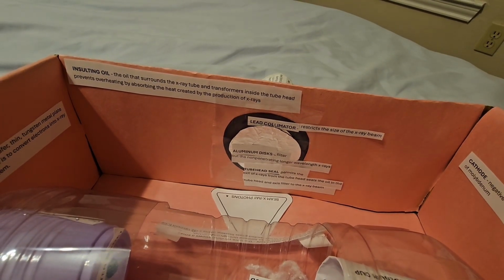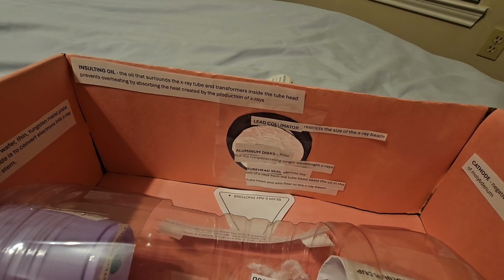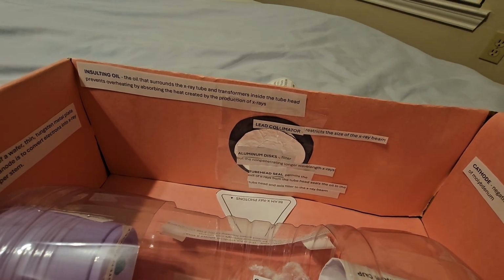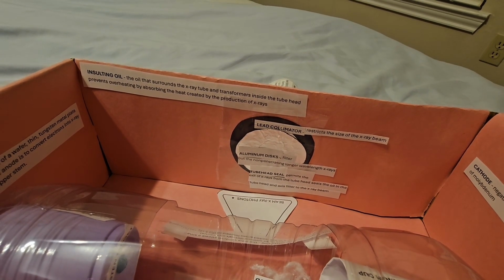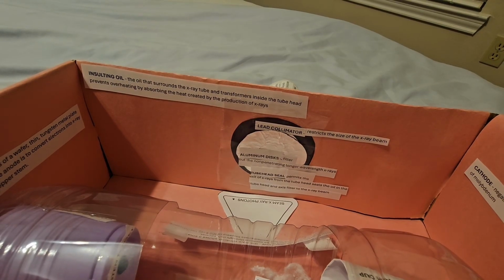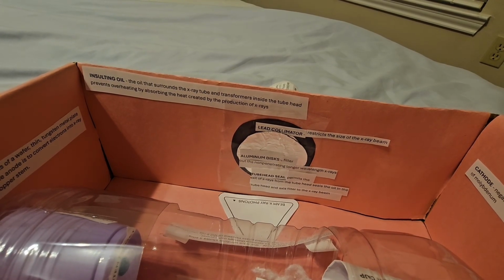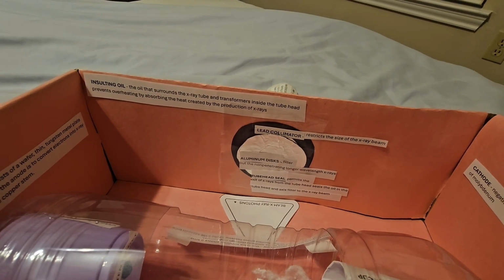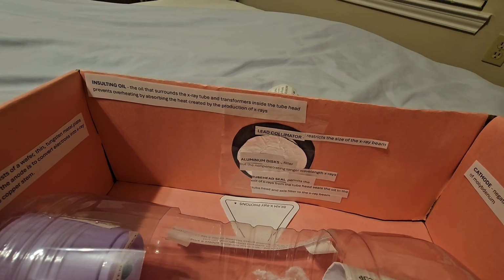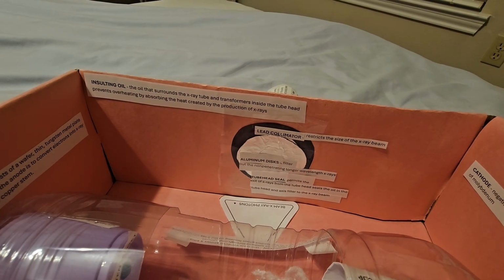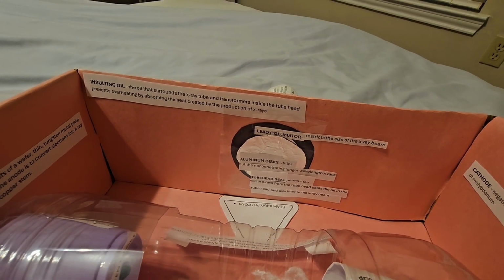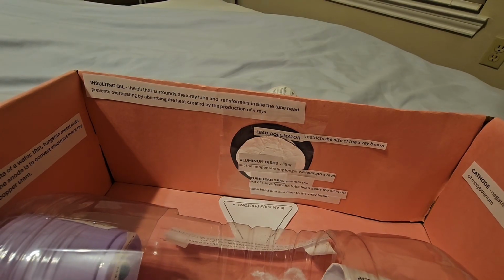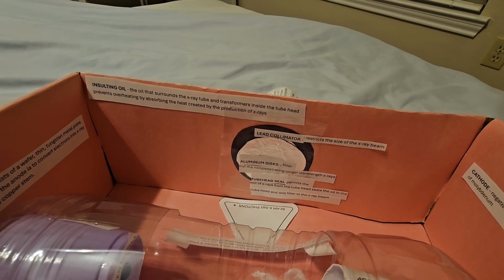Once the X-rays are produced, they leave the tube head by passing through a series of components. First, they go through aluminum discs, which filter out the low-energy, non-penetrating X-rays. Next, they pass through a lead collimator, which restricts the size and shape of the X-ray beam. Finally, the X-rays exit through the PID, which directs and aims the X-ray beam towards the patient.